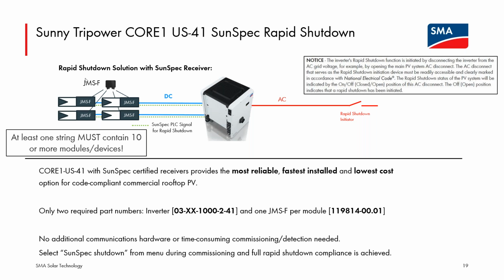In this diagram, we're showing the JMSF SunSpec certified rapid shutdown receiver being used. This device is not made by SMA, but there is an SMA part number for it. So if you talk to BayWa, ask for the SMA price list. There actually is a part number on the SMA price list for this specific SunSpec certified rapid shutdown receiver element. We did that to make sure that folks could source these very easily, even though it's not an SMA part, it has an SMA part number.